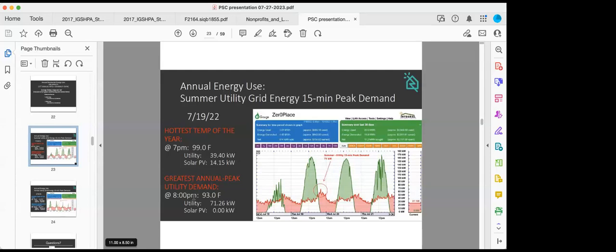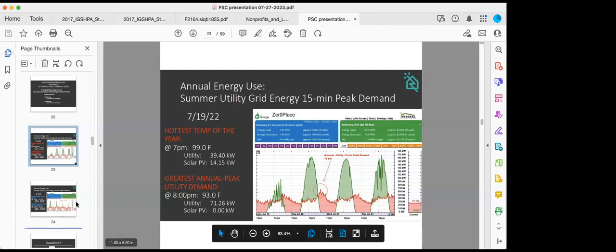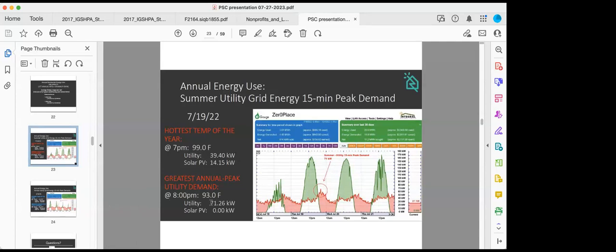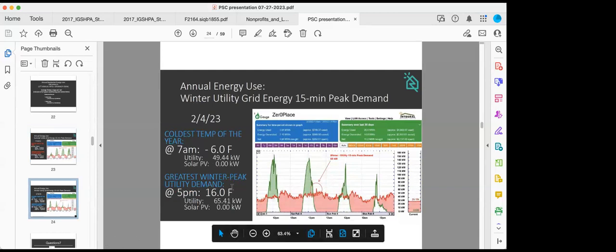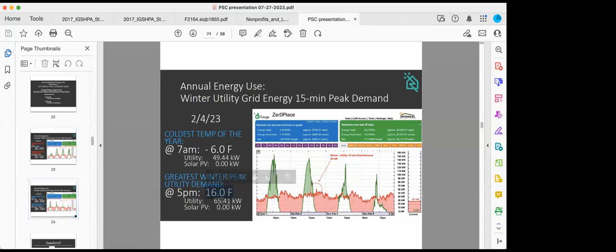Now, what do you think is going to happen to the winter load? That was the shocker. The summer load for an average building here in Buffalo, the load requested from the utilities for a same size building was 1,000 kW. Here, the peak in summer for the entire building, with all accessories, appliances, elevators, everything, was only 71 kW. Now comes winter, and you'd expect that to be much higher, right? Absolutely wrong. The winter peak occurred in the evening of the peak day, at 17 degrees Fahrenheit, and it was only 65 kW.